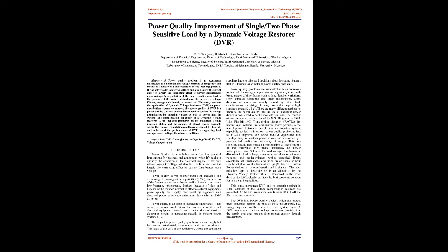It not only relates largely to voltage but also deals with current, and it is largely the corrupting effect of current disturbances upon voltage. A degradation of the power quality may lead to the presence of voltage disturbances like sag/swells, voltage flicker, voltage unbalance, harmonics, etc.